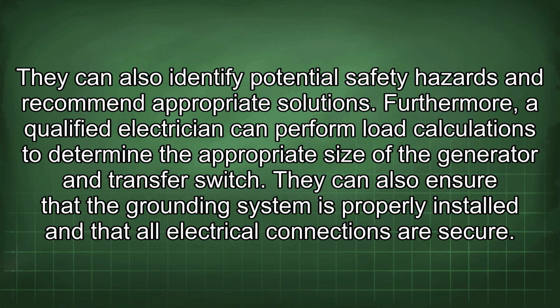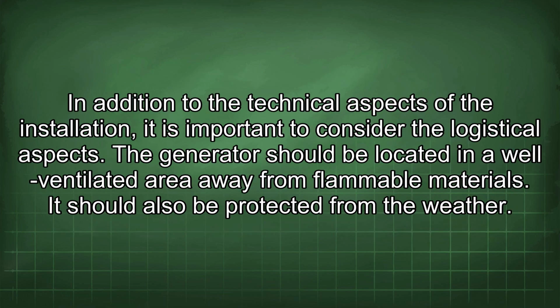Furthermore, a qualified electrician can perform load calculations to determine the appropriate size of the generator and transfer switch. They can also ensure that the grounding system is properly installed and that all electrical connections are secure. In addition to the technical aspects of the installation, it is important to consider the logistical aspects. The generator should be located in a well-ventilated area away from flammable materials.